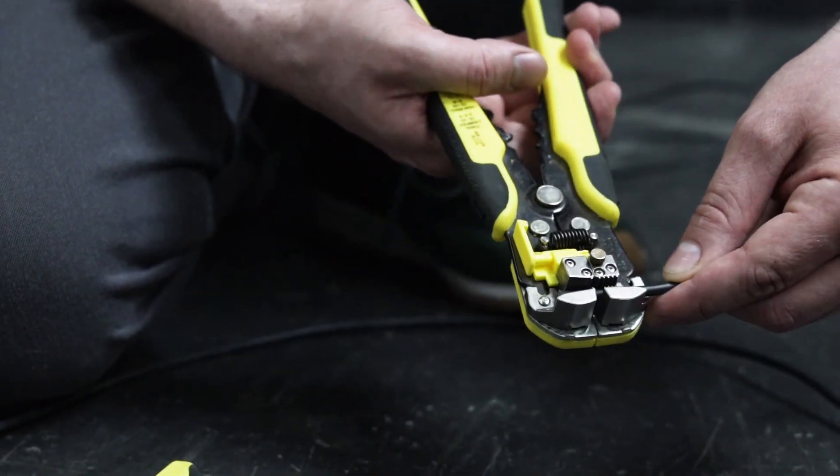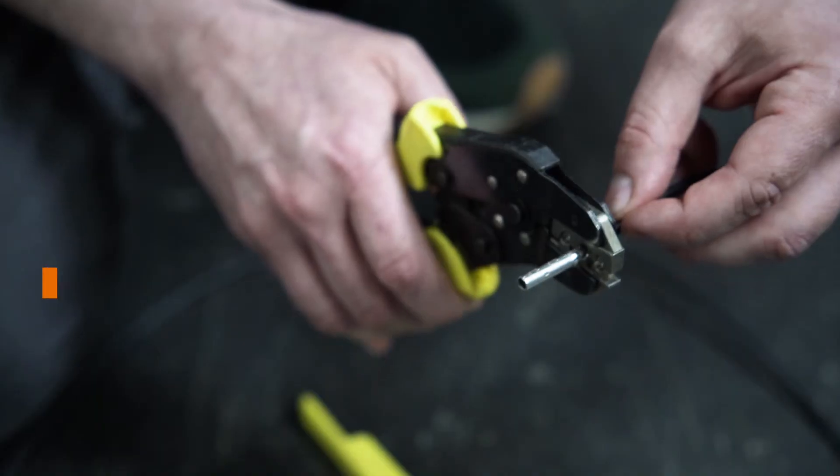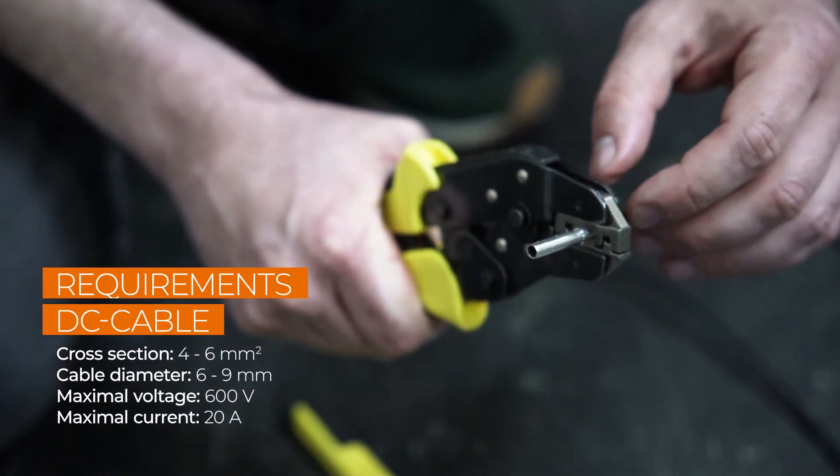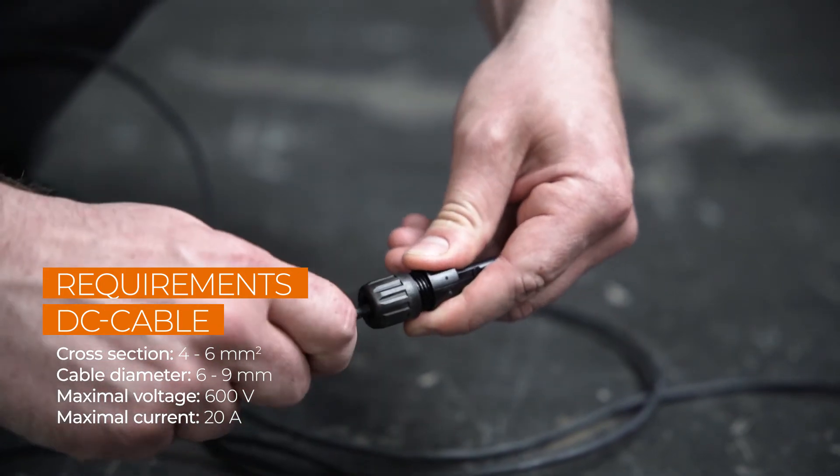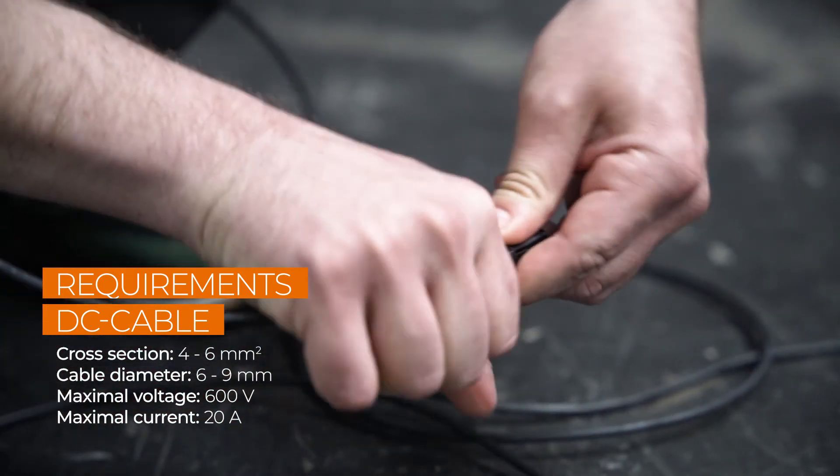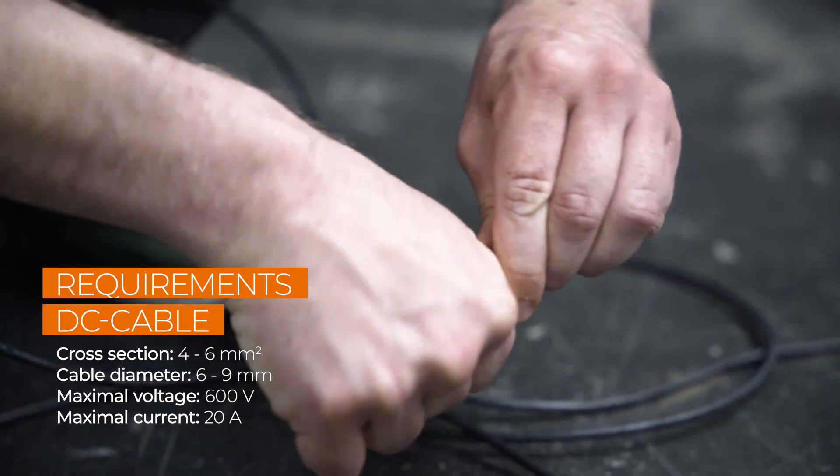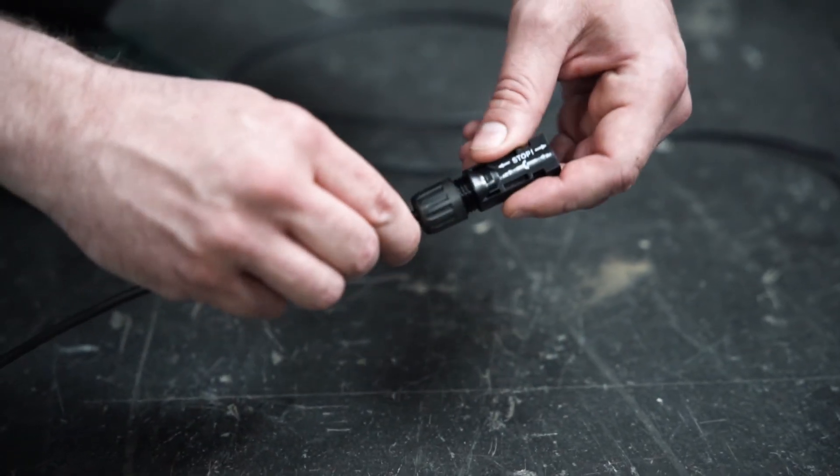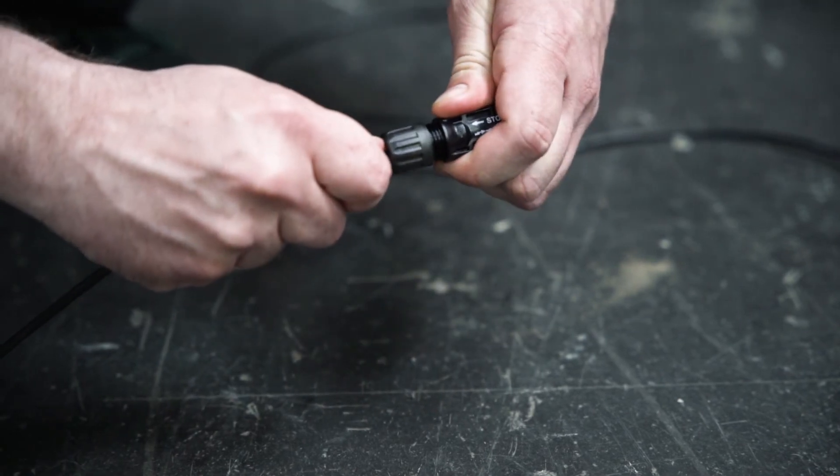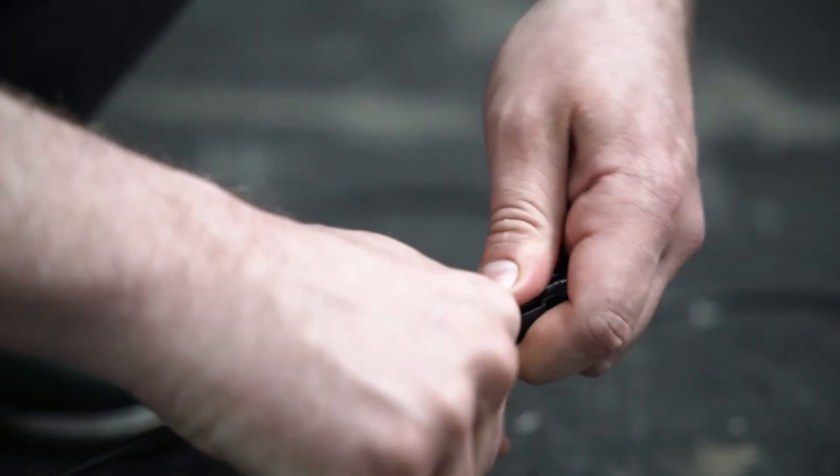Now let's take a look at the DC connector. After stripping the insulation, you have to attach a crimp contact. For this, you have to check the polarity, because each pole has different terminals that need to be crimped. The polarity is marked on the inverter. Then push the cable into the insulating sleeve until it snaps into place. Screw it and that's it.